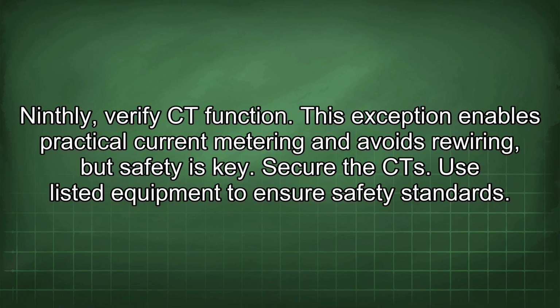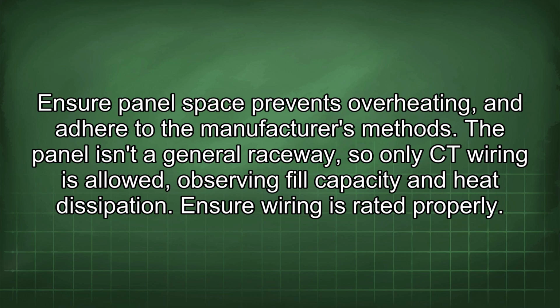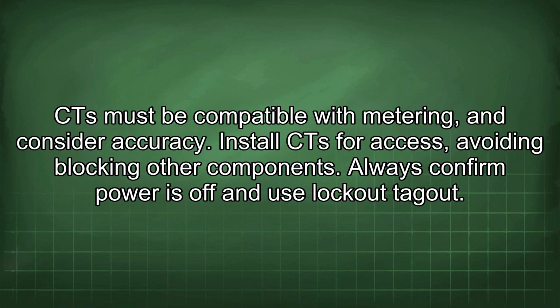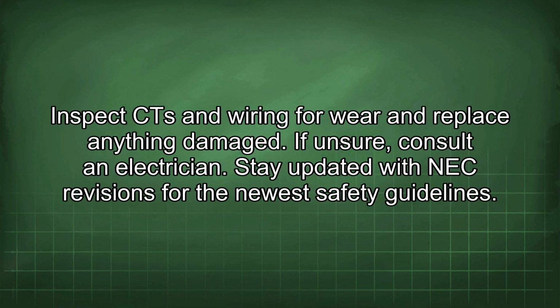Secure the CT. Use listed equipment to ensure safety standards. Ensure panel space prevents overheating, and adhere to the manufacturer's methods. The panel isn't a general raceway, so only CT wiring is allowed, observing fill capacity and heat dissipation. Ensure wiring is rated properly. CT must be compatible with metering and consider accuracy. Install CT for access, avoiding blocking other components. Always confirm power is off and use lockout tagout. Inspect CT and wiring for wear and replace anything damaged.